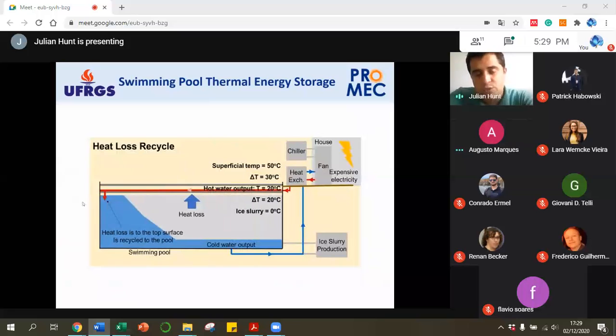I found a solution that substantially reduces heat losses, mainly on the surface of the pool where it's highest. When you return the hot water used to cool your house, its temperature comes back around 18 to 20 degrees, and you return it on the surface of the pool. This means the surface, at 20 degrees, creates only a 30 degree difference between the pool and outside temperature instead of 50 degrees, which lowers surface heat loss by half.